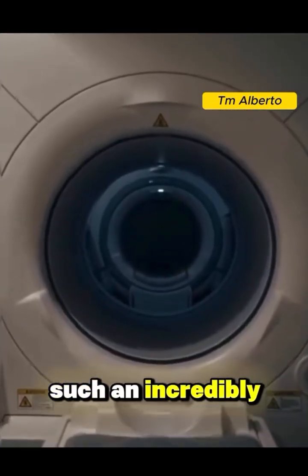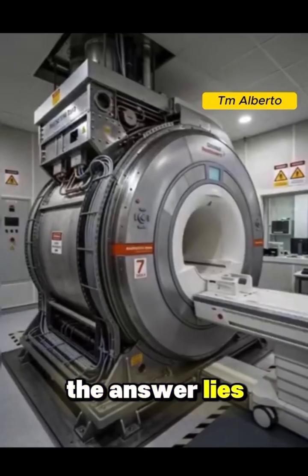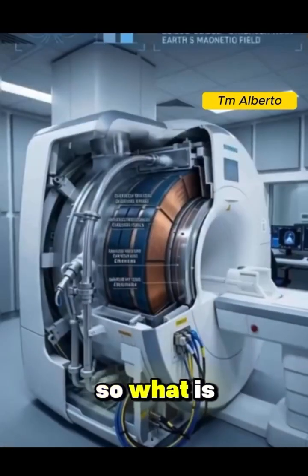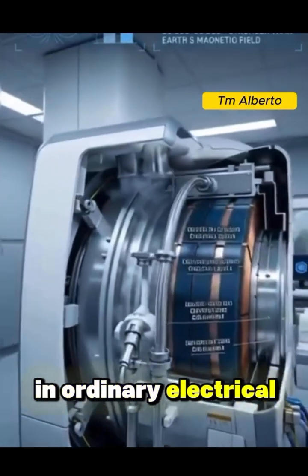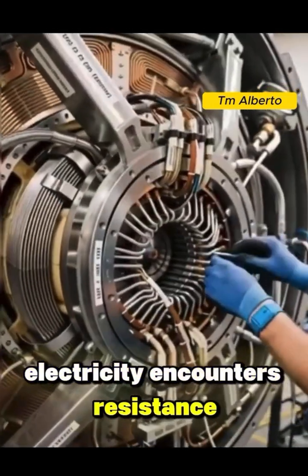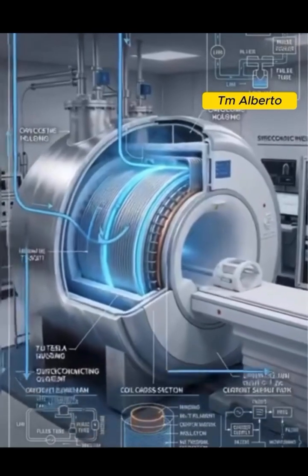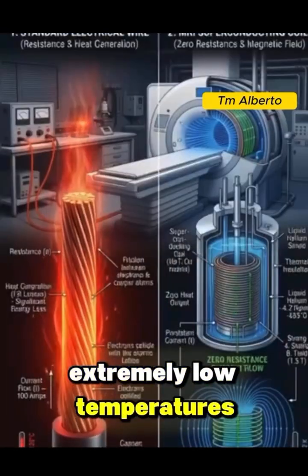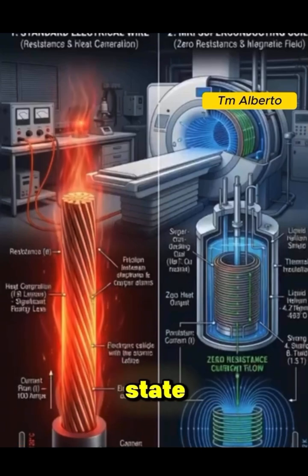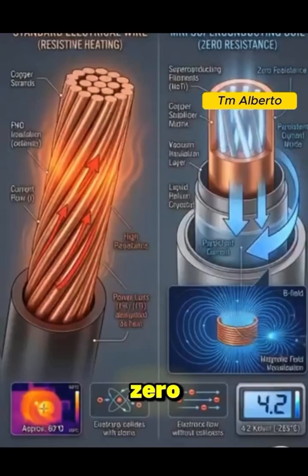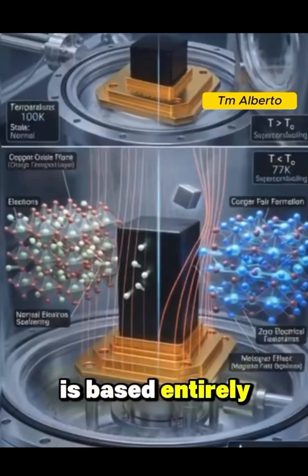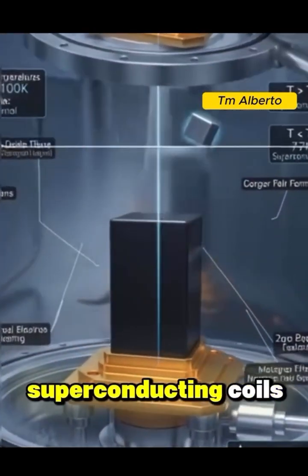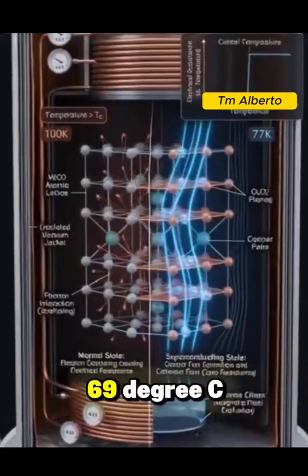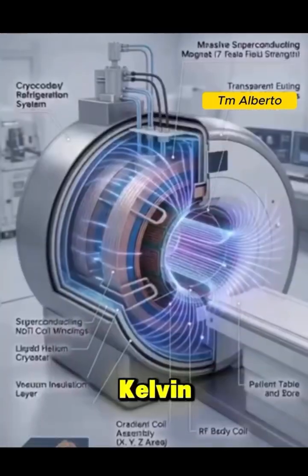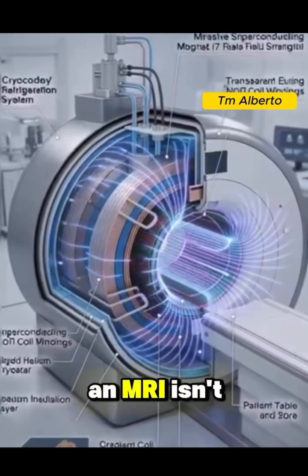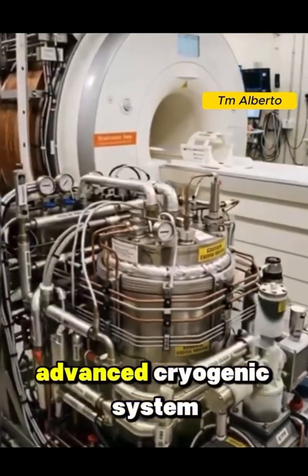But how is such an incredibly powerful magnet built? The answer lies in superconducting coils. So what is a superconductor? In ordinary electrical wires, electricity encounters resistance, causing energy to be lost as heat. But certain materials, when cooled to extremely low temperatures, enter a superconducting state, where their electrical resistance becomes almost zero. The MRI magnet is based entirely on this principle of physics. That's why its superconducting coils are cooled to approximately -269°C, or about 4 Kelvin, using liquid helium. In other words, an MRI isn't just an imaging machine, it's also an advanced cryogenic system.